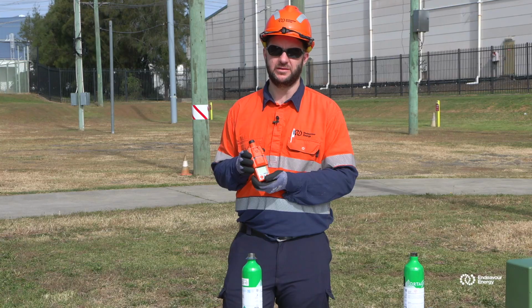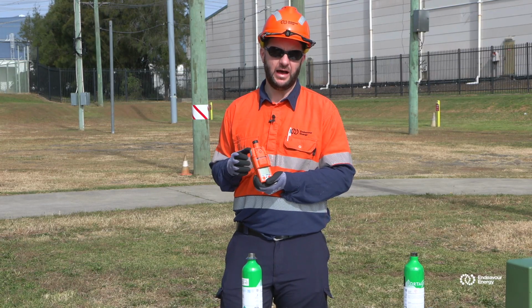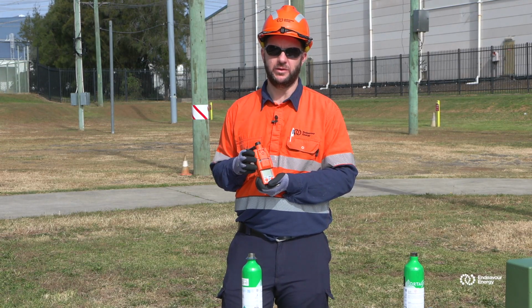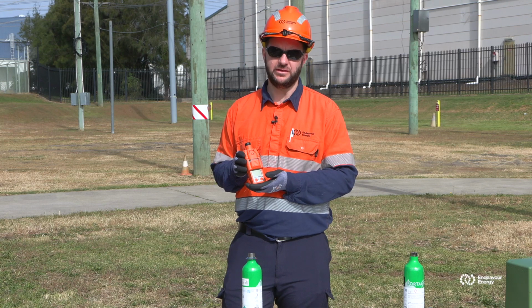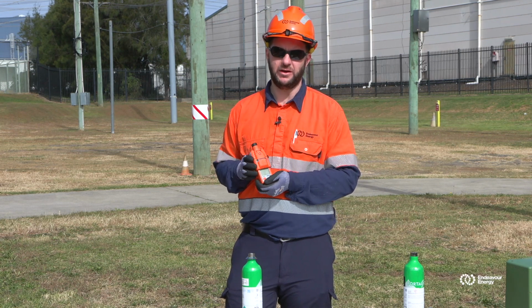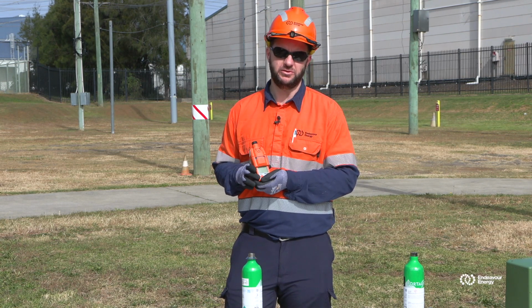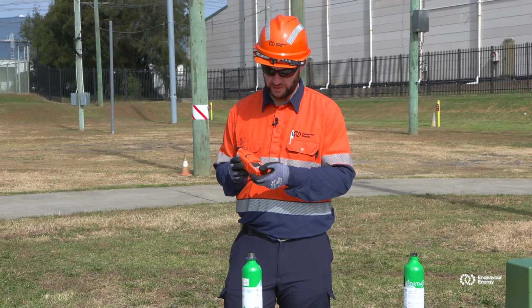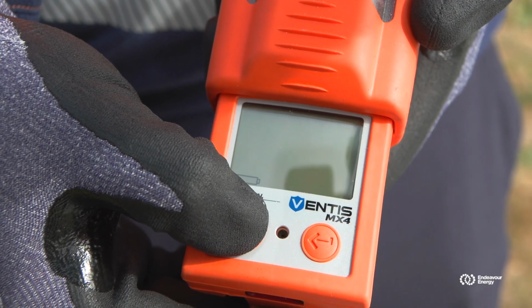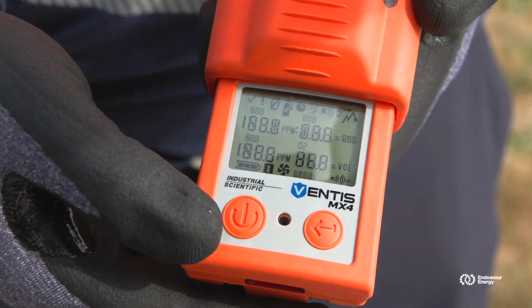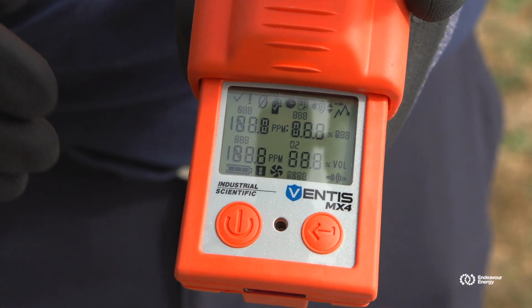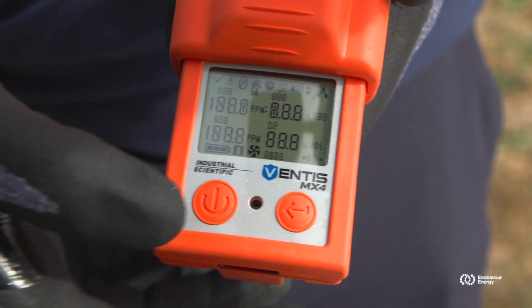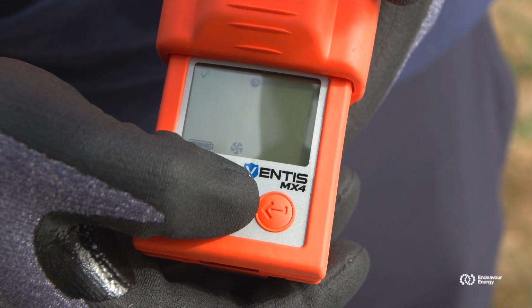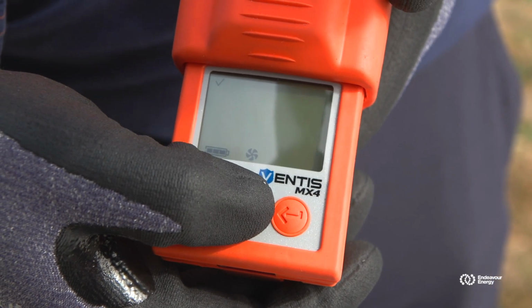It'll take a little bit to start, and once it goes through its startup process, it has a 20-second countdown. During the startup process, we just want to make sure we have adequate battery life, so we'll check the battery indicator as it's going through. So to start now, we'll hold the power button, then we'll get a read on the digital display. We have the battery pop up, and you can hear the pump starting to work now, and the gas detector is going through its startup procedures.